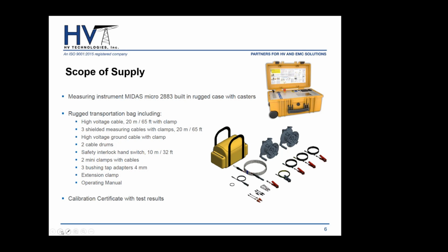So when you order a MIDAS Micro 2883, you will get the following. You will get your instrument, the one box design, lightweight, 55 pounds. Also, you will get a transportation bag. Now, in this transportation bag, you will have your high voltage cable, 65 feet in length with your clamp, which is this one here. You'll have 3 shielded measuring cables with their clamps, which are these over here. A high voltage ground cable, which is the one that goes to the yellow port on the instrument. You will get 2 cable drums. On one, you can, for example, put your high voltage cables. On the other one, usually you have all 3 measuring cables in one drum, and that way you can quickly clean up after a test.